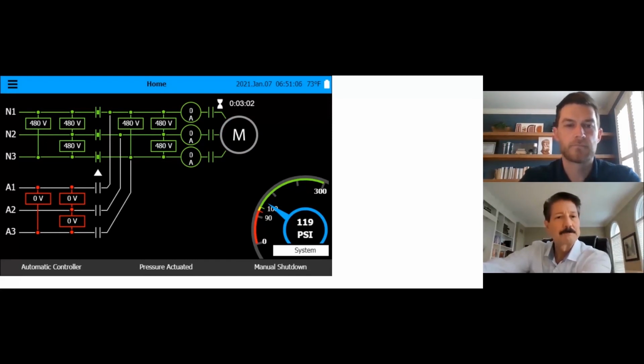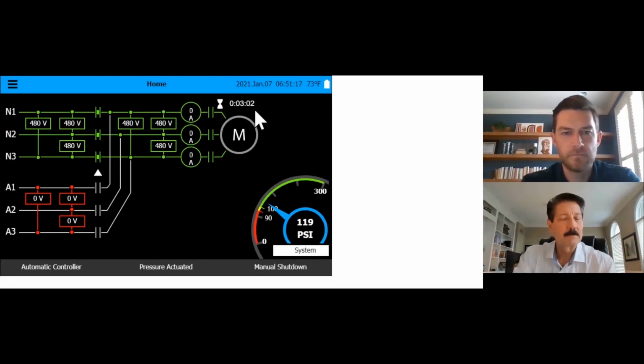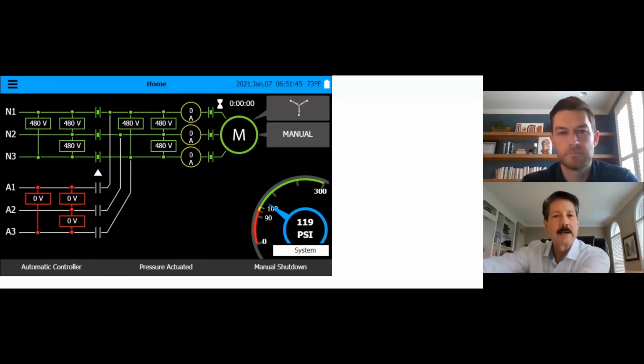Now I'm going to do a start here. Oh, okay, and here's one other point I want to show you. We ran this for 3 minutes and 2 seconds. So it will keep a running record, and this is quite nice because when you're flowing water and you're doing a startup test, you know, half the battle is knowing how long you've run the pump. And military like to run it a little bit longer than what you normally would for a commercial building or, you know, a distribution center, what have you. But that is an easy way of tracking how long it actually has operated. Then you can shut it down, let it cool down a little bit. So what I'm going to do is press this and you tell me how it started.